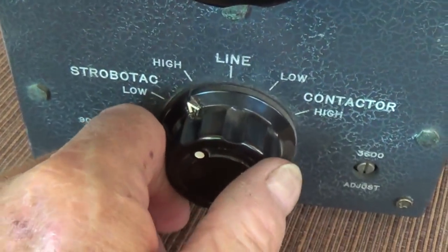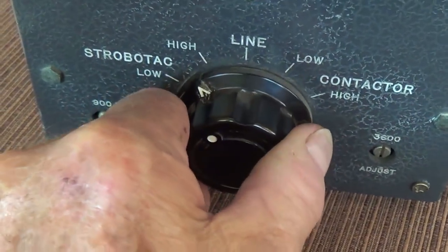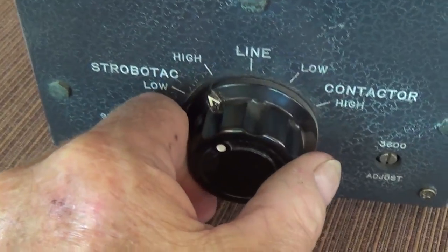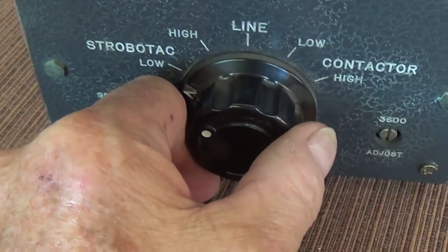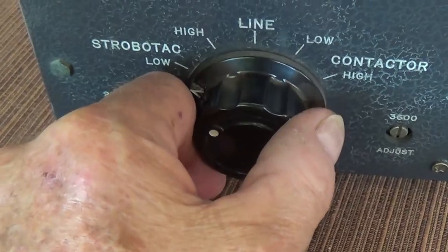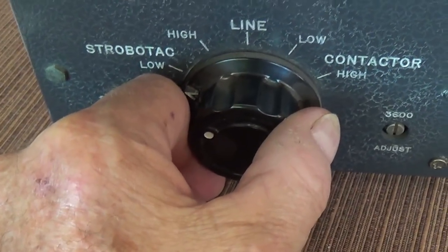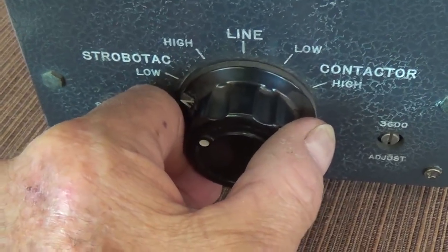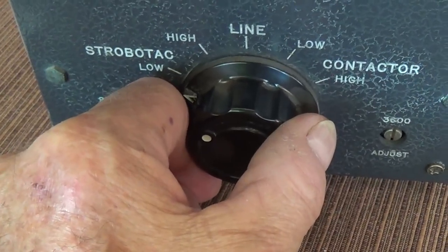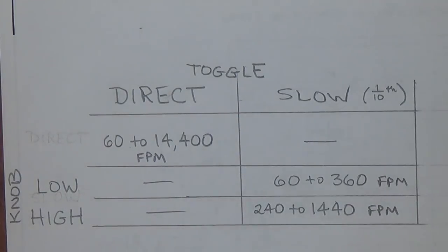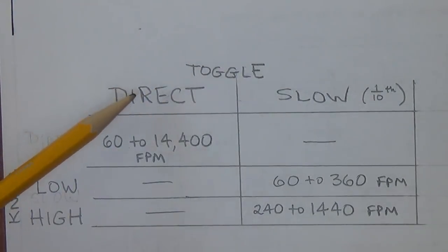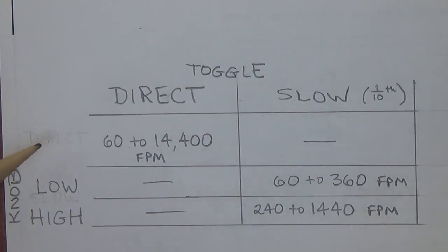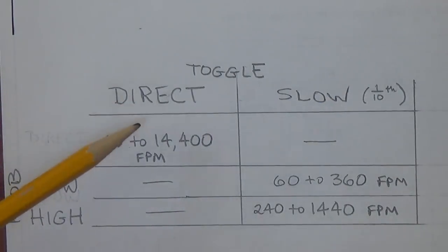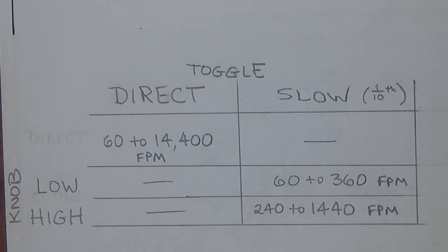1,440 FPM. So as you can see, when we're in the slow mode with the toggle switch on the back, we will use the instrument then to measure speeds that are about 1/10 what we would measure if it was in the direct position. So direct is for high speed measurements, slow is for low speed measurements. Since all of that is utterly confusing, I made a quick chart here to show, depending on the toggle position, direct or slow, and the knob position, low or high, we have 3 different speed ranges.